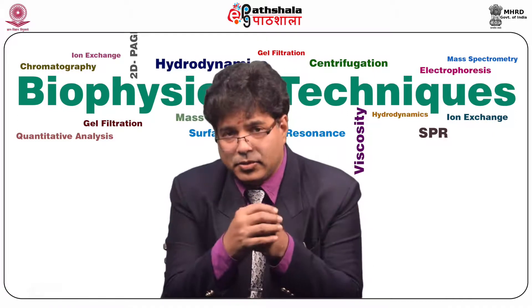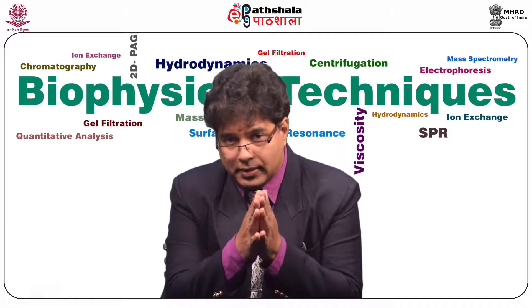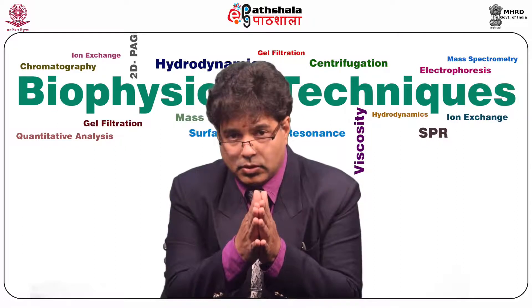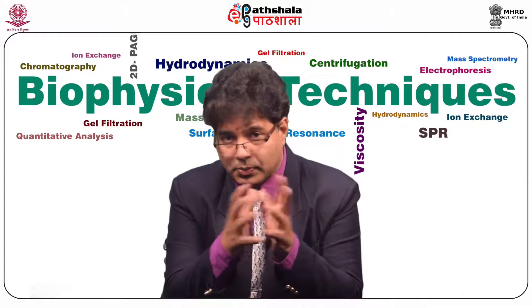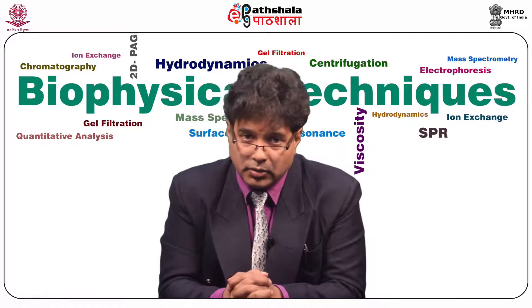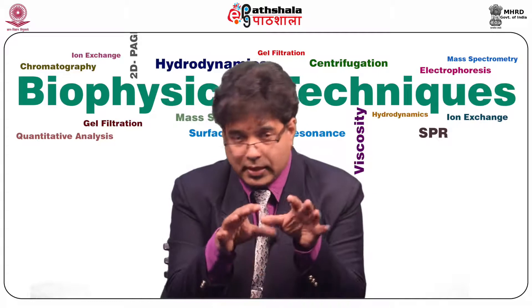The major types of mass spectrometers can be broadly classified into three categories: magnetic field deflection, quadrupole mass spectroscopy, and time of flight. In magnetic field deflection, ions as charged particles are deflected by a magnetic field in vacuum. Quadrupole mass spectrometry is a significant development where electric potential is applied — positive or negative potentials deflect the charged ion path. The quadrupoles are four rods arranged in a square through which the charged particle passes.